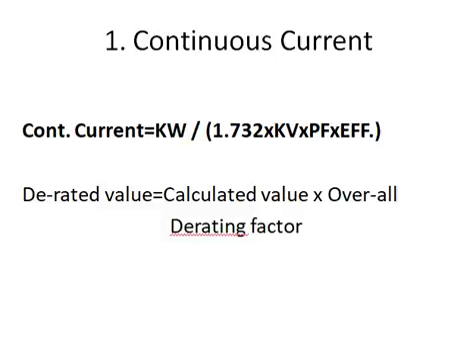The derated value of the motor feeder equals the calculated continuous current rating multiplied by the overall derating factor. We then need to check with the cable manufacturer catalog for preliminary selection of the cable size and the number of runs. This completes step one.